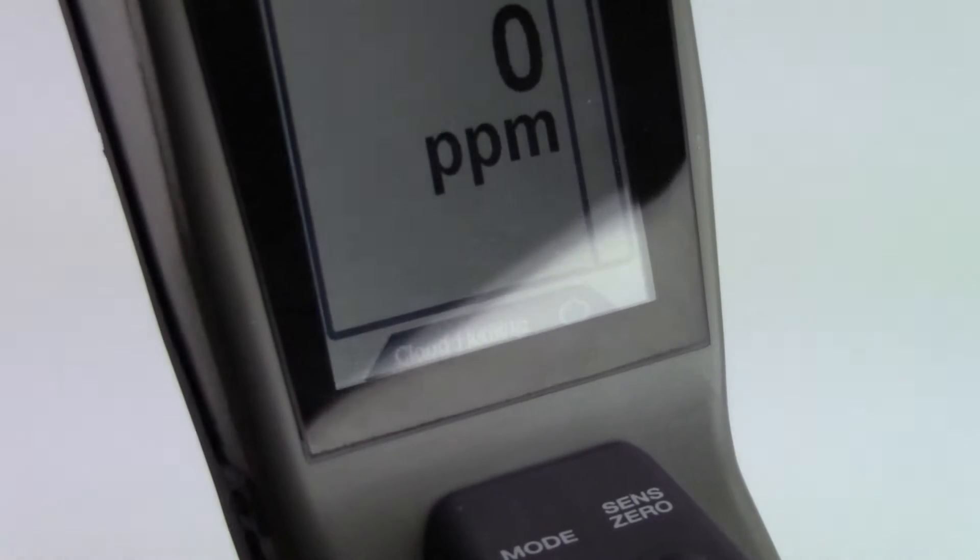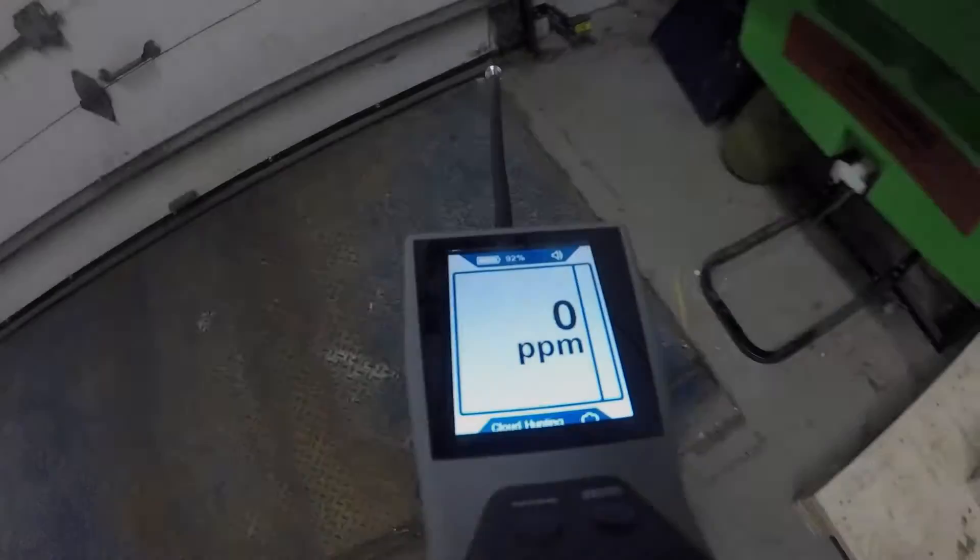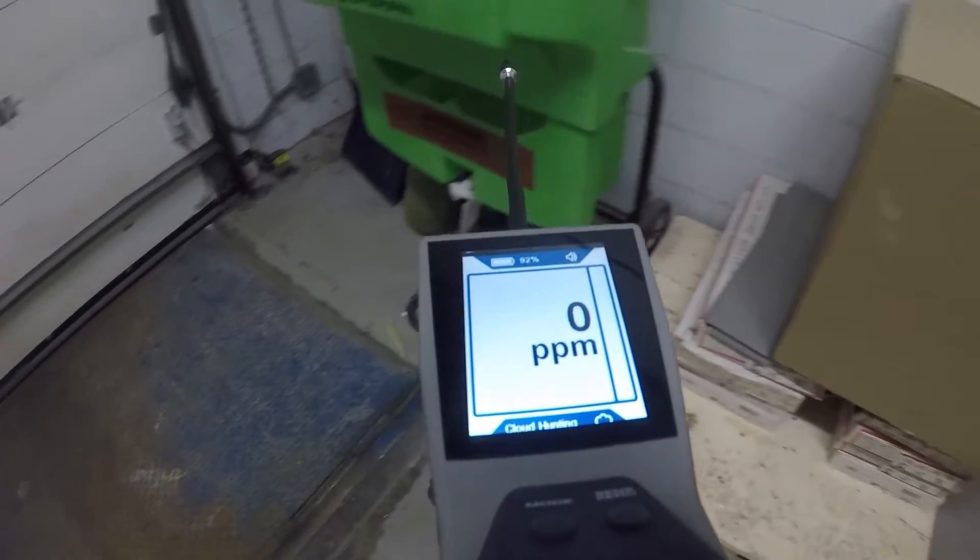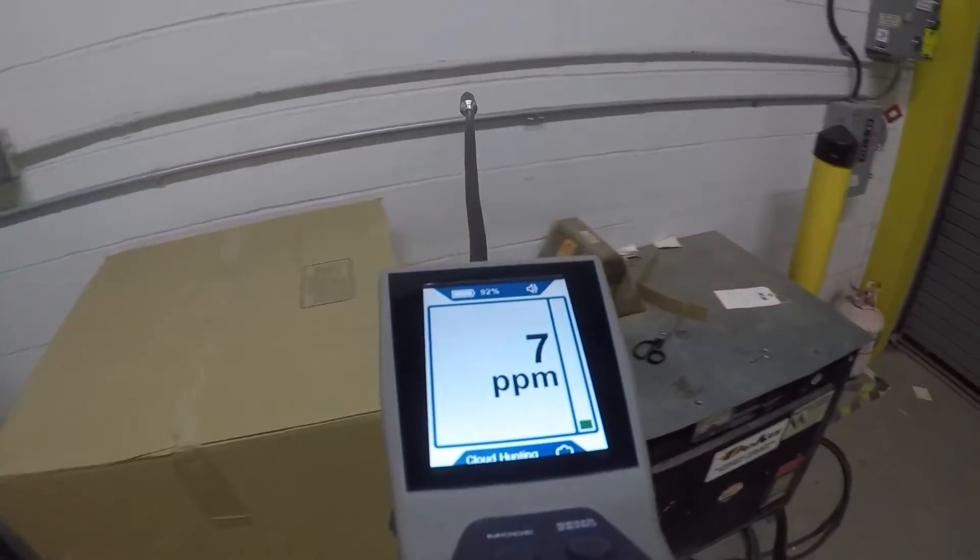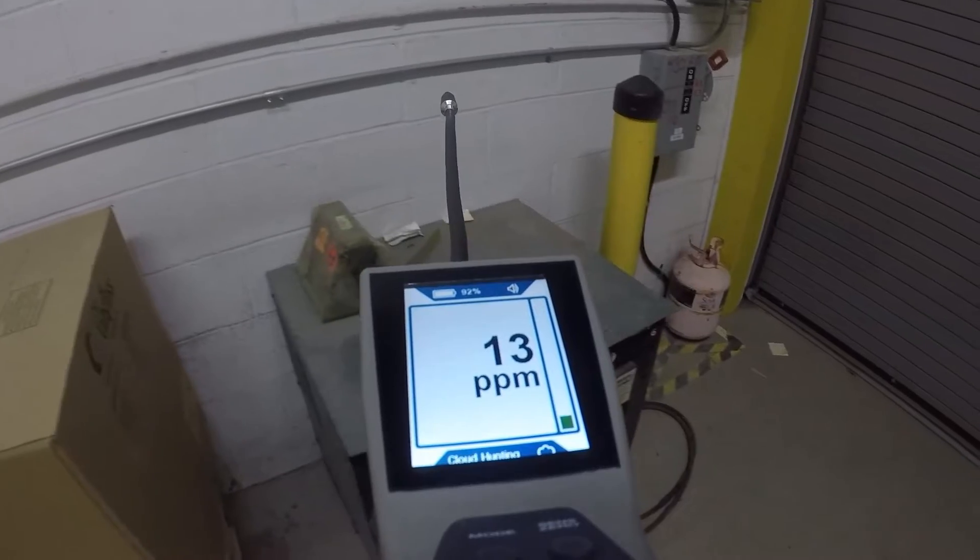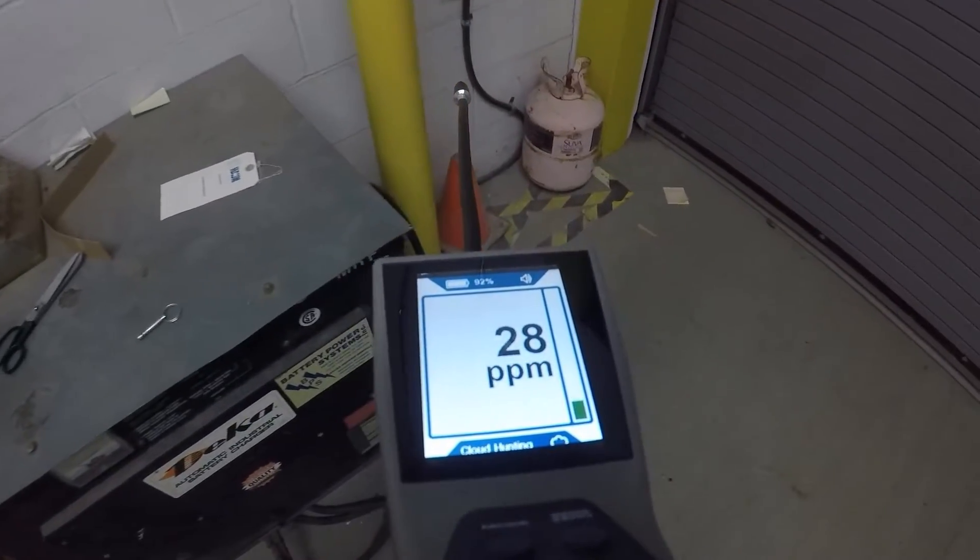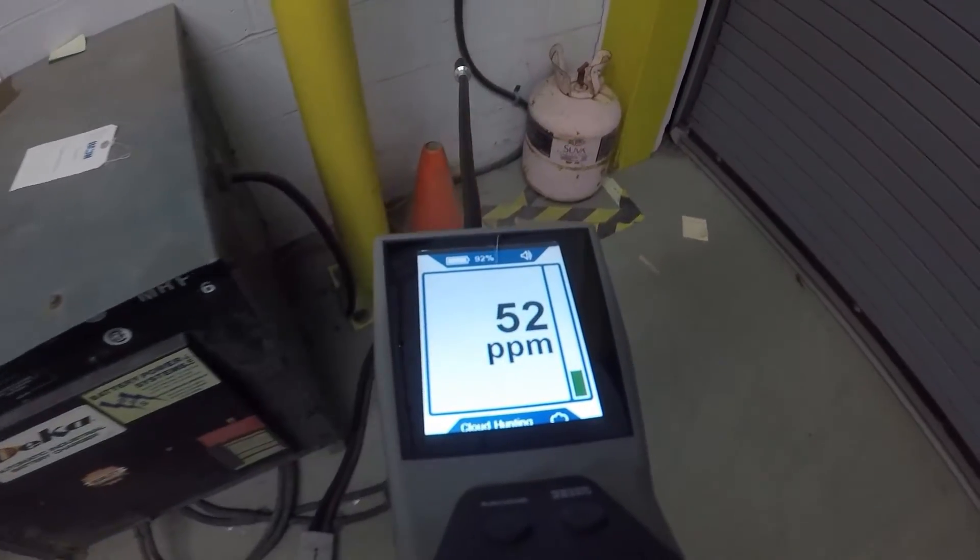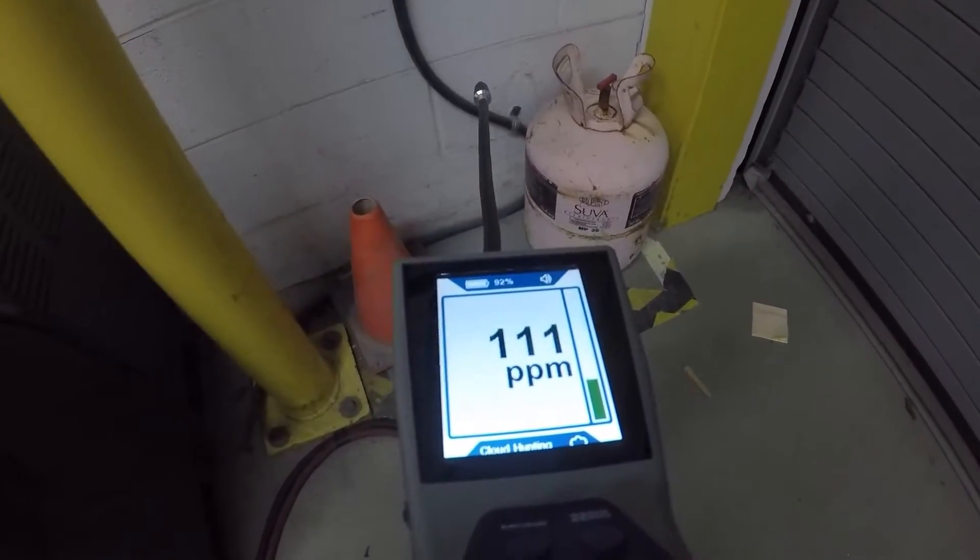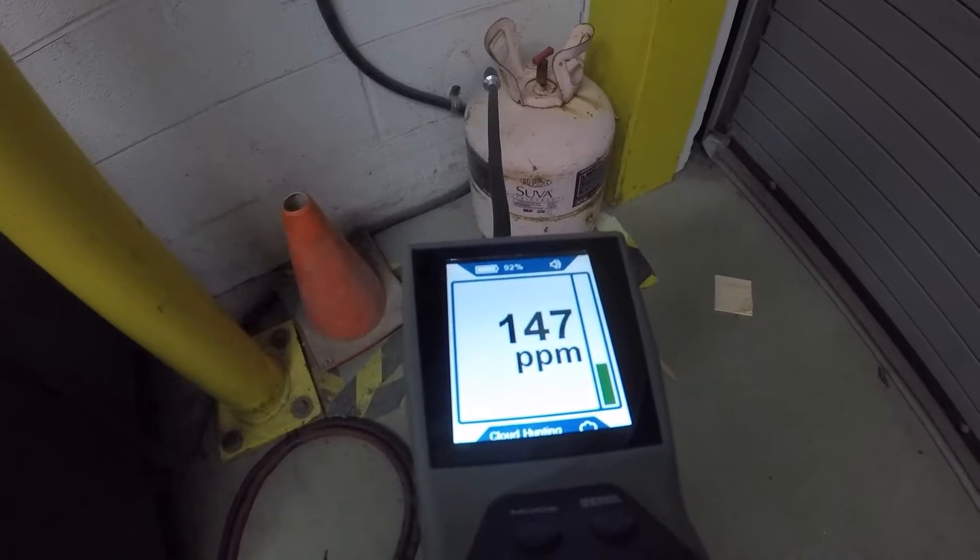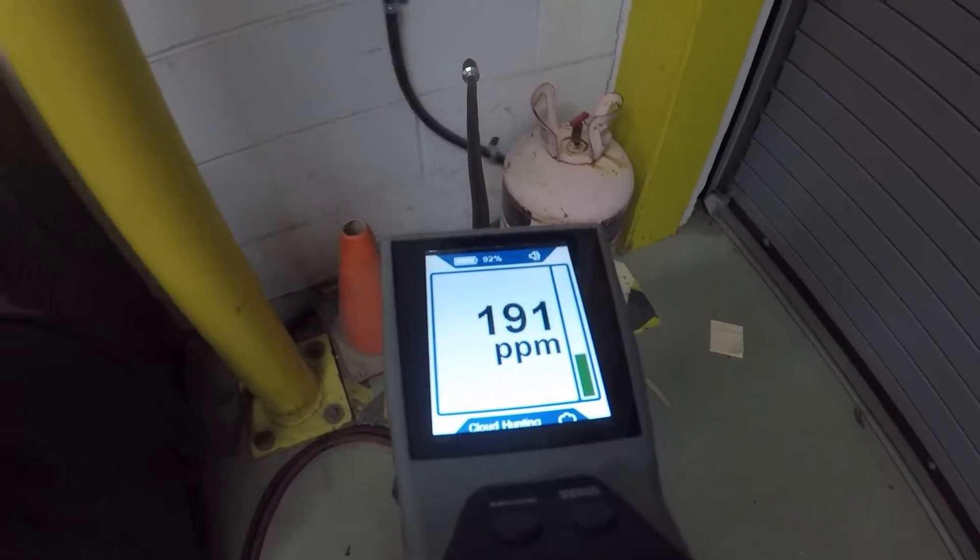Cloud hunting mode uses a PPM readout to help you navigate through the cloud of refrigerant. To use cloud hunting mode, slowly move through the suspect areas and observe the PPM reading. The higher the PPM, the closer you are to the leak source.